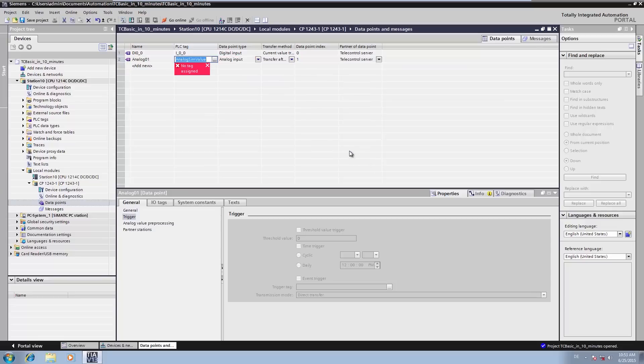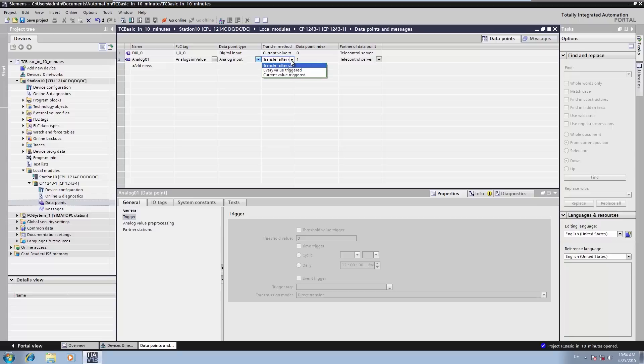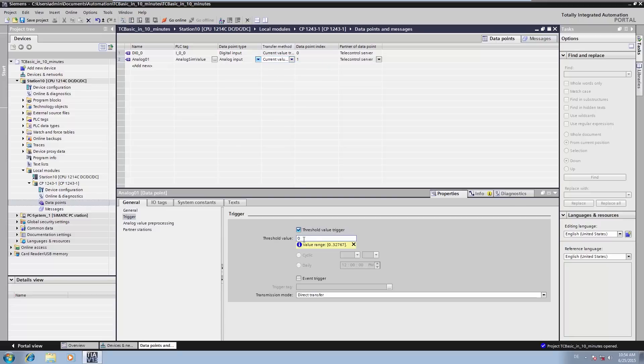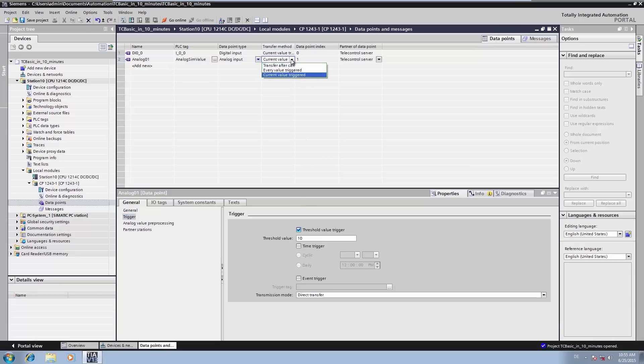As you can see, the TIA Portal is already trying to select the proper data point type for you. We then specify the transfer conditions to also enable event-driven transmission of this analog value: current value triggered, threshold value active. Because our simulated measured value is operating in a range between 0 and 1000, we select a threshold value of 10, which corresponds to 1% of the measuring range. When needed, the data point can also be configured so that it is buffered in case the connection is lost. For this purpose, we select the setting Every value triggered.